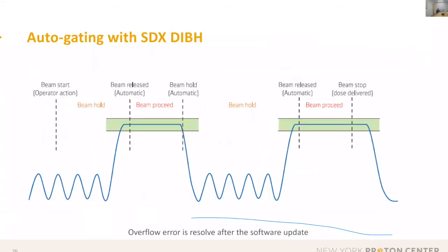So, talking about auto gating. The SDX system first requires 3 consecutive regular breath patterns. That means over here, and then it gives the green light, saying okay, you can start the breath hold, and that will be indicated on the glasses. The patient will see that. And before that, you can request the beam, and you can even see beam on, because the interface will control the beam.